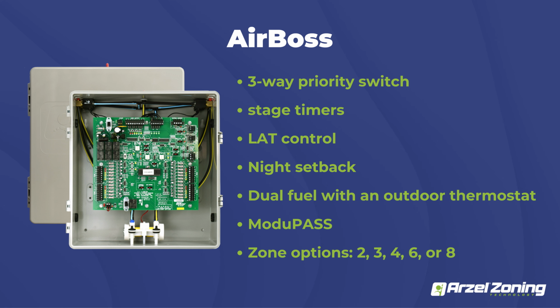So if you guys had a commercial job and you've got 8 different zones on there and they're running 8 different thermostat programs, when the last person leaves for the evening, they could either have a night setback or they can physically flip that switch. And instead of running all those programs in that whole building and wasting all that energy to keep them at a satisfactory temperature, we could revert it to that zone 1 to save that customer on their fuel efficiency and set the lower temperatures for when nobody's in that building for the evening.